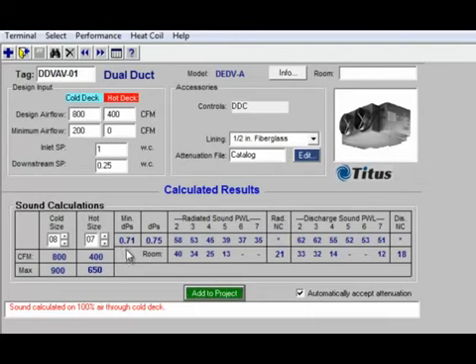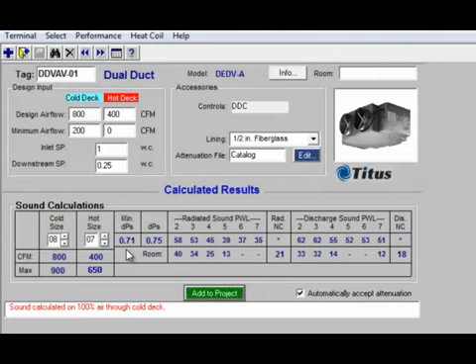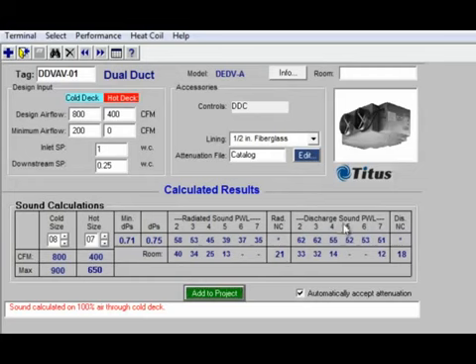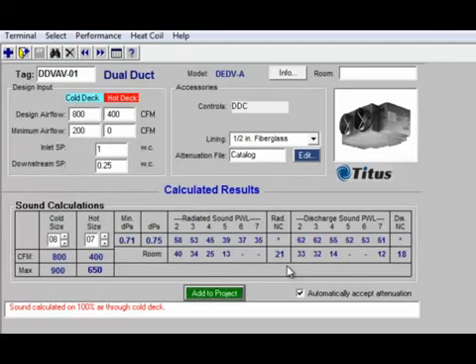After selecting fiberglass lining and making a selection, the unit came up with mismatched inlets — that's not unusual when you have dual duct boxes in a variable volume application, since we need more air for cooling than for heating, so the hot duct is smaller than the cold duct. The minimum pressure requirement is 0.71 inches, which is much higher than a single duct VAV box. That's because dual duct boxes with mixing chambers have to blend hot and cold air together using mixing baffles and sometimes perforated plates to generate turbulence. Sound-wise, our radiated sound level is NC 21 and our discharge sound level is NC 18 — both very low levels that would be acceptable even in a conference room in a standard office building, let alone a healthcare application.